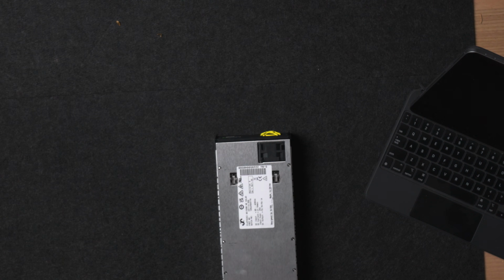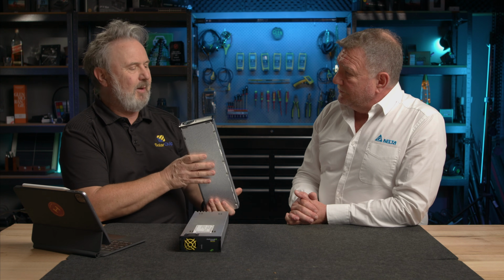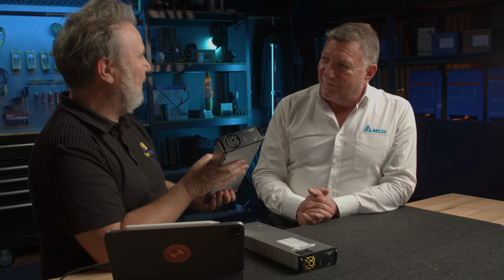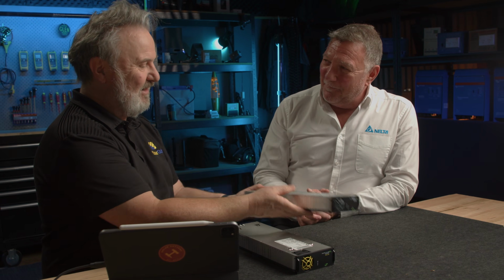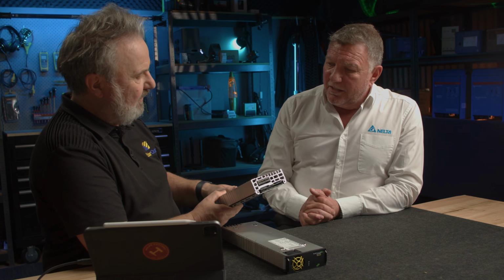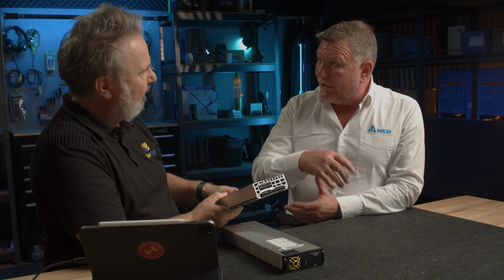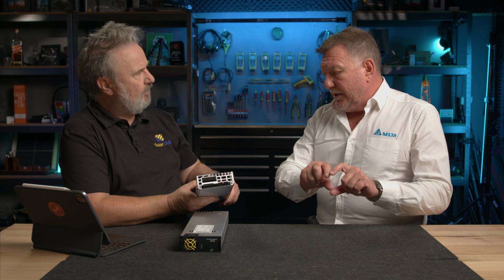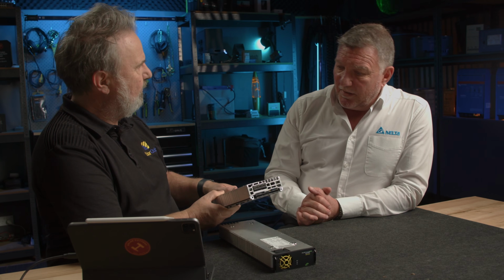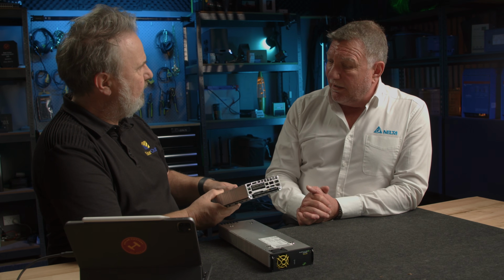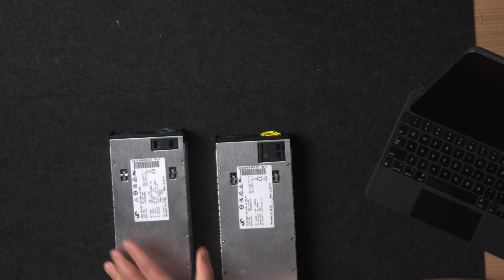Frankly, this is so small. I can remember installing inverters of similar power rating which took nearly 2 people to lift to put on the wall, and now we've got these tiny little units which just plug in at the back here. So you've just got a back plane that these all plug into? Correct, yep. Hot swap, load sharing too, of course. When we have a look at the system later on, we'll see a number of these across different power racks. The good thing is, if there is a failure for some reason, which is very rare, you just pop it out.